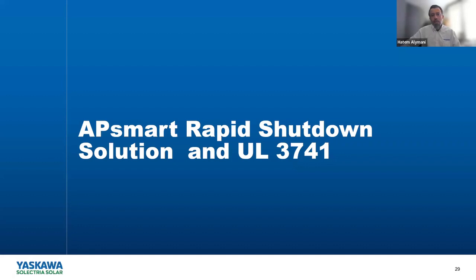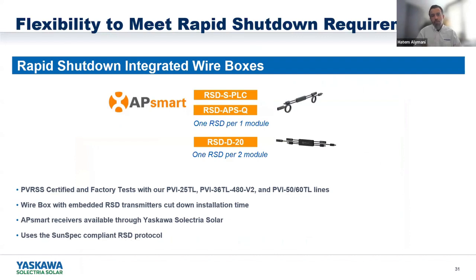Discussing rapid shutdown devices on the roof and rapid shutdown solutions and UL 3741. As we mentioned, our inverters are compatible with APsmart rapid shutdown solutions. We have 2 rapid shutdown solutions, which is either 1-to-1, so 1 rapid shutdown device for each module, or the other one is the D20, where you can put up to 2 modules per rapid shutdown. And please make sure that you are using the correct rapid shutdown device. If you are using the first rapid shutdown device, then it has to be 1-to-1. You're not going to be able to use 2 modules per 1 rapid shutdown device. We've seen, unfortunately, some of our customers use a Y connector and force 2 modules into 1 rapid shutdown, and that will create issues with the rapid shutdown. Most likely the rapid shutdown will fail within a few weeks or a few months. So please try to avoid forcing the rapid shutdown to receive more modules than it can handle.